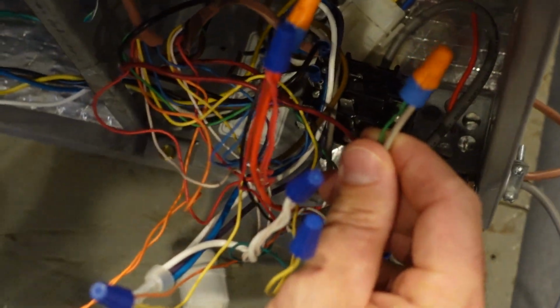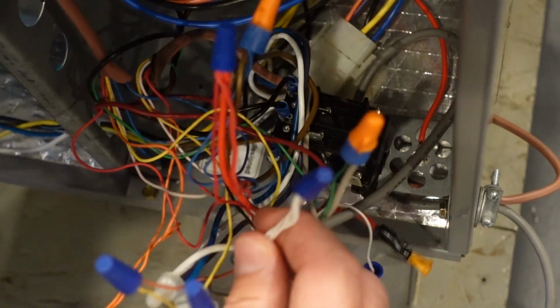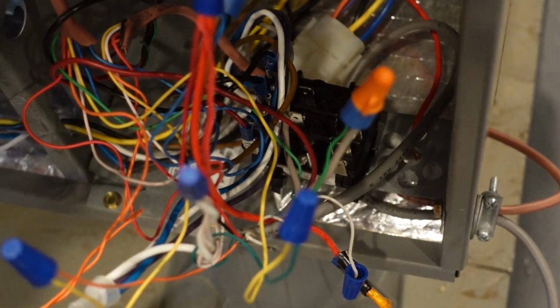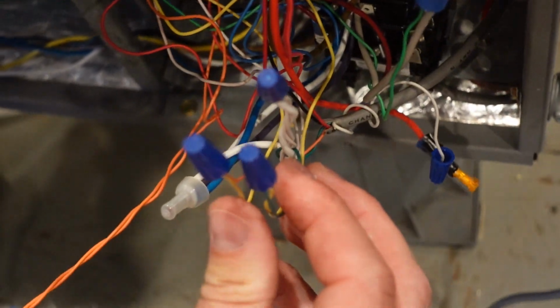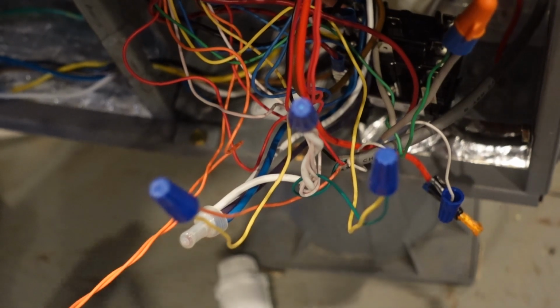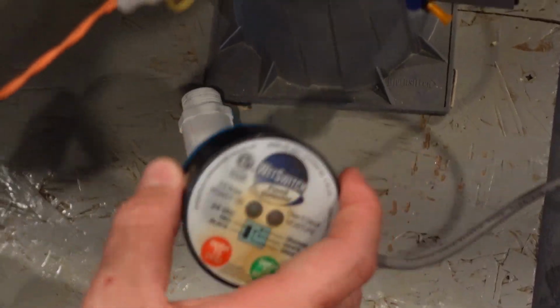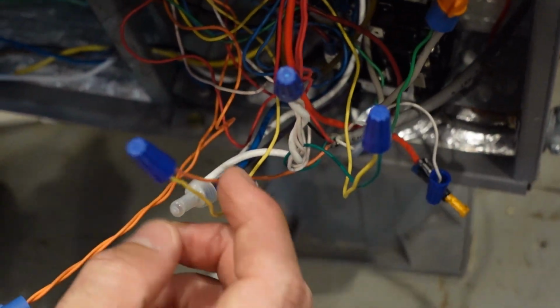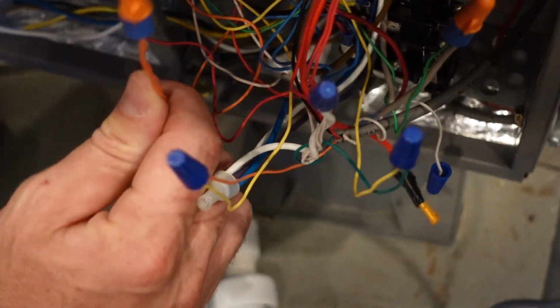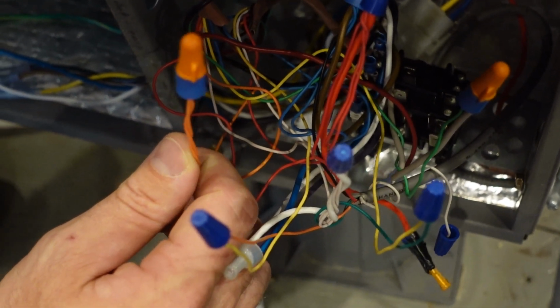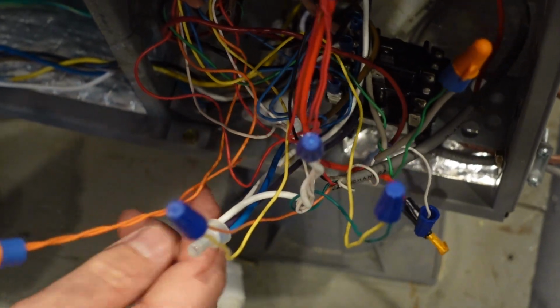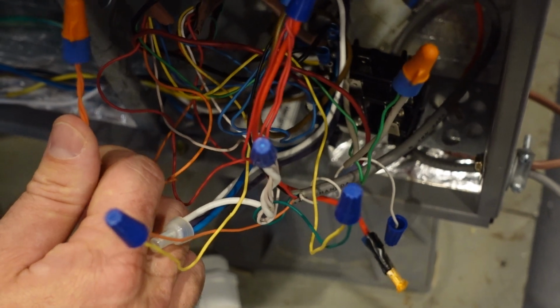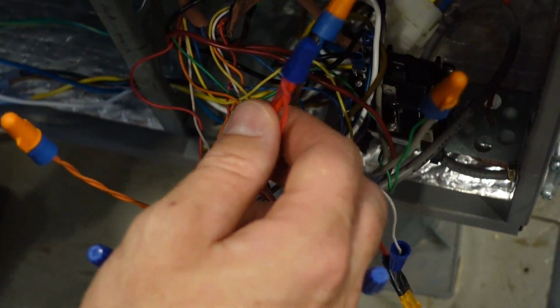I then have my G terminal, or indoor fan, and my W terminal, which is for my heat kit right here. My indoor fan obviously is right here, going back to that. And then my Y terminal, which runs my compressor, is bypassed through this wet switch. So if this wet switch gets any water on it, it'll break the signal. It's very common to see on indoor units that are located in an attic or closet. And then finally we have the O terminal, which is orange. That's typically the color we will always use for that. So when you're talking about terminals, don't address them as the orange terminal. It's the orange wire used for the O terminal. It's the red wire used for the R terminal.